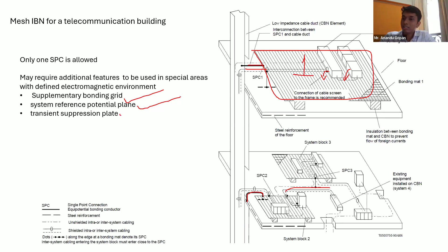Or you can have a transient suppression plate. Basically, all incoming power and signal lines will come through this plate, which is interconnected with the reinforcement, and there will be SPDs along this plate. This reduces the lead length of the SPD, giving you effective working SPDs.